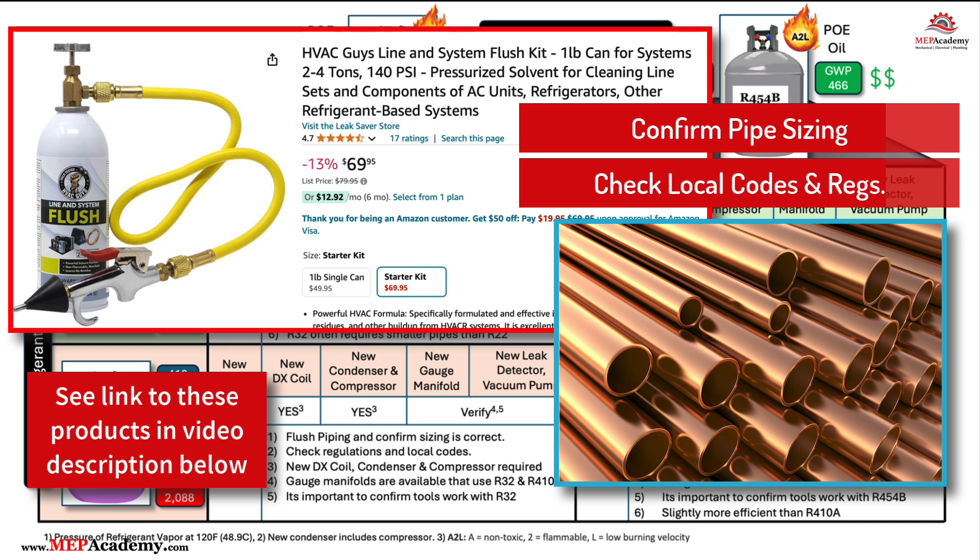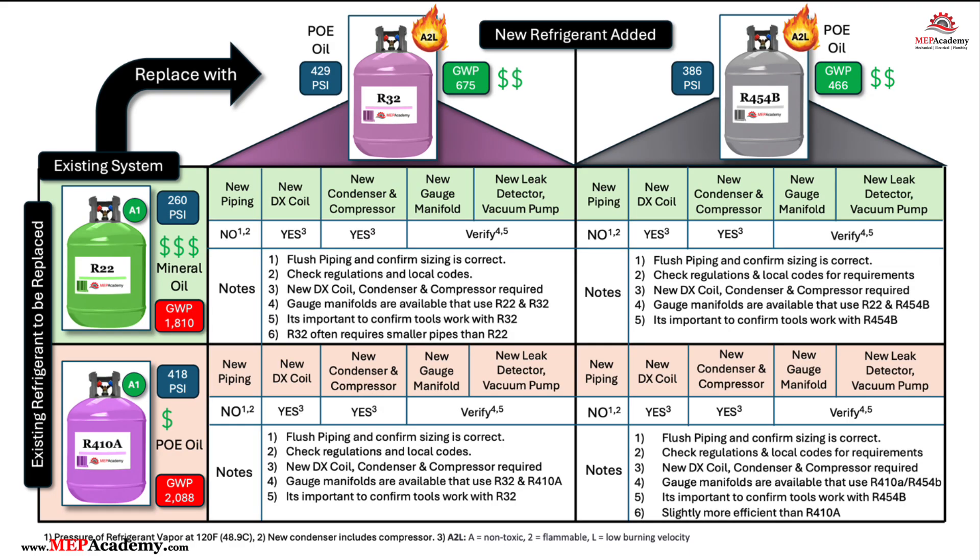R454B, like other A2L refrigerants, requires the use of specific lubricants, such as POE oil, that are compatible with the new refrigerant. The system may need to be flushed to remove any incompatible oil or residue before charging with R454B. Additionally, the piping should be carefully inspected for leaks and pressure tested to ensure it can handle the operating conditions of the new refrigerant. If the existing piping is in poor condition or not properly sized, replacement may be necessary.